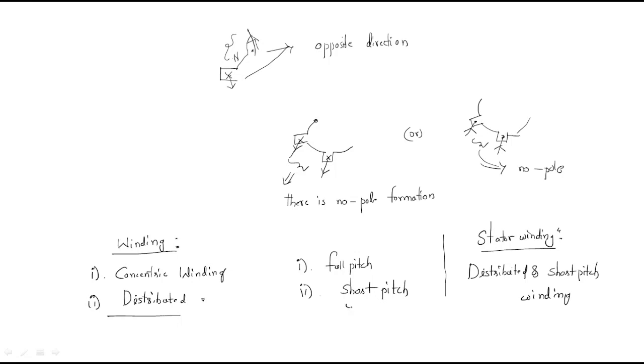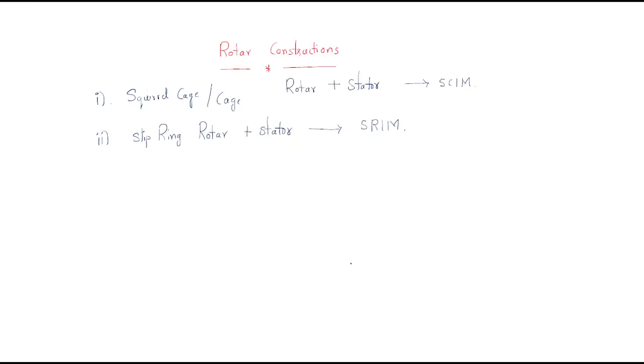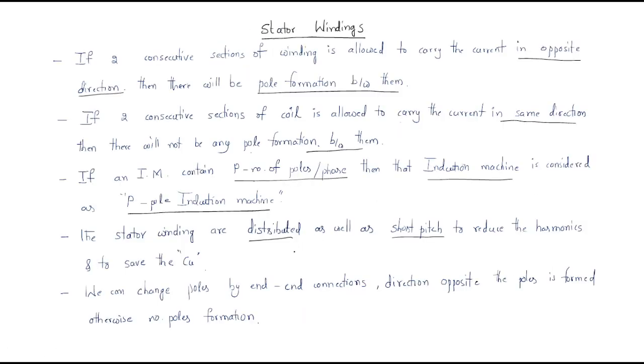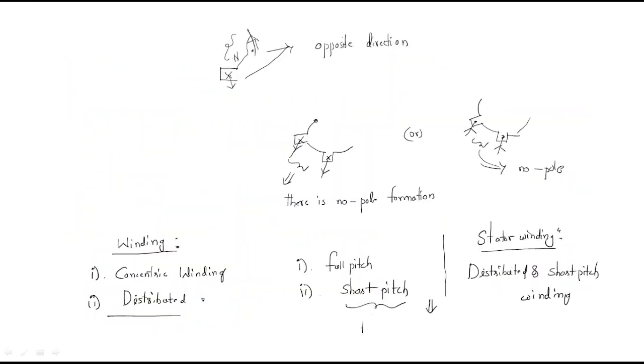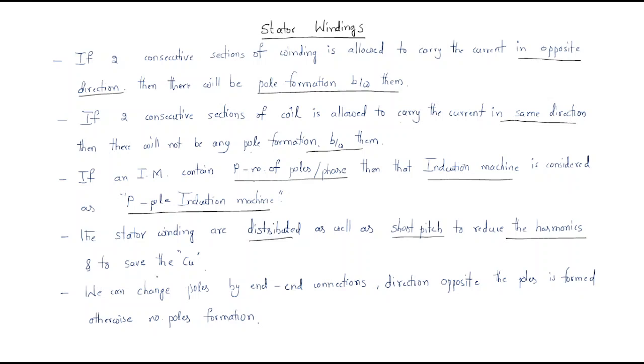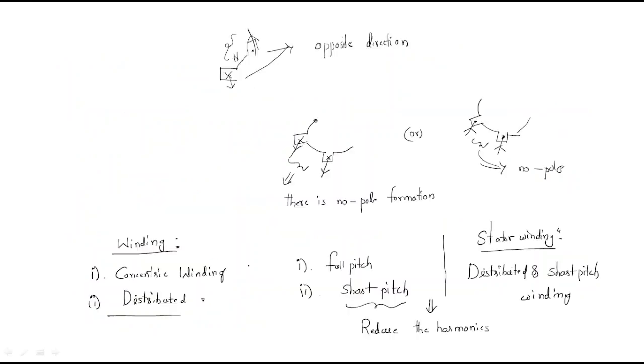By using distributed and short pitch winding, the main advantage is that it reduces harmonics. Harmonics are unwanted frequencies, and this winding configuration reduces them. The other important advantage is saving copper: for full pitch winding the complete copper length is used, but for short pitch winding the copper length is decreased.